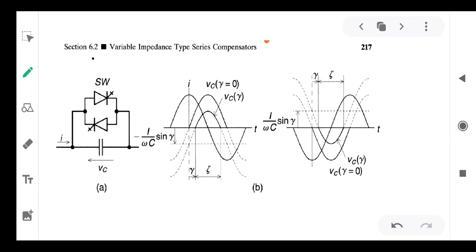Now let me explain the GCSC. Anti-parallel GTOs are connected across the capacitance. So the anti-parallel combination of GTOs will act as a switch. When the switch is on, the capacitor is bypassed and the voltage across the capacitor is 0. When it is turned off, the capacitor will be in circuit and there will be some voltage across the capacitance. Therefore, it will inject a series voltage with the line. So series compensators are nothing but injection of voltage in series with the line. Thereby, by turning off the GTOs, the capacitor will be in the circuit. When turning on the GTOs, the capacitor will be bypassed. This logic is used to control the capacitor voltage, thereby the voltage injected with the line.